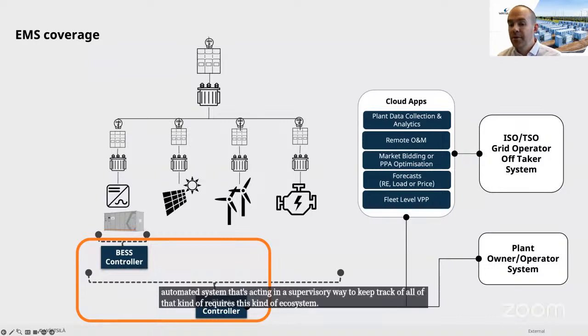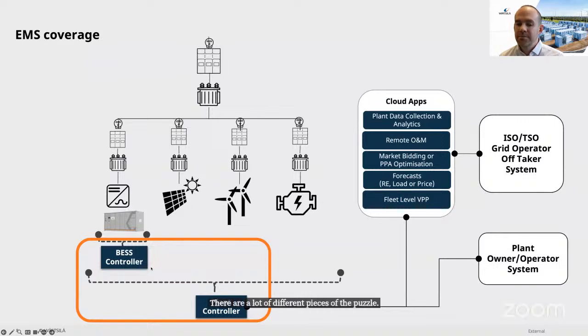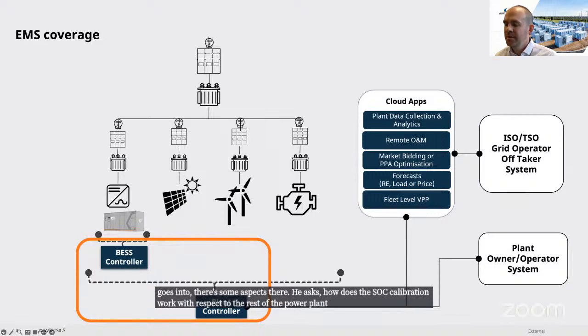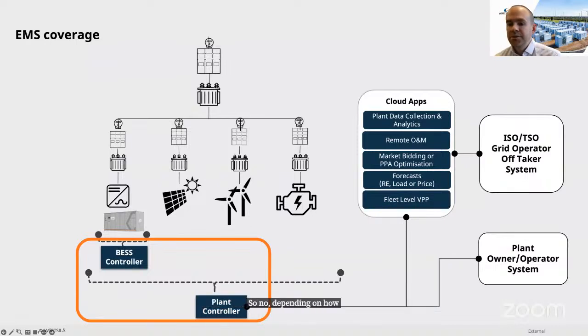And so there are a lot of different pieces of the puzzle in terms of how your vendors plan to provide a balanced system continuously. Luis's question goes into some aspects there. He asks, how does the SOC calibration work with respect to the rest of the power plant? Do you need to have all the BESS units charging in order to measure the calibrating unit? So no, depending on how long it's been since calibration, units in a modern EMS should be arbitrarily and/or hierarchically selected for calibration in an opportunistic way.